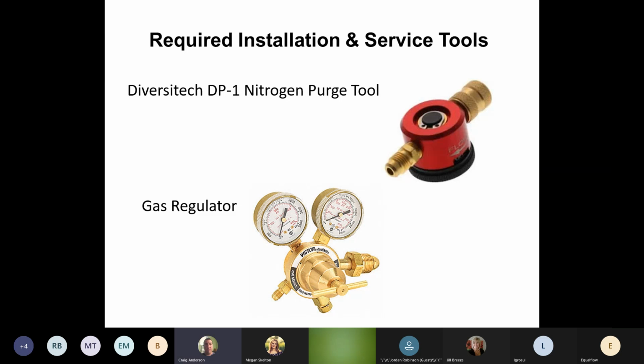Couple other things out there, little nitrogen purging tool, great little tool. There's no setup on your nitrogen tank. You put it through this little thing and it monitors the amount of nitrogen going through your system so you can do a proper weld. We want nitrogen going through the system. It keeps the pipes clean. If we're not cleaning the pipes, then we're getting flaking of the inside of the copper, and that's going into our screens and the meshes that are on the EE valves and stuff like that and blocking them off. So make sure you got a nice little purging tool. There's nothing to set up. You turn it to purge. It monitors the amount of gas that's going through your line. So great little tool for when you're welding.